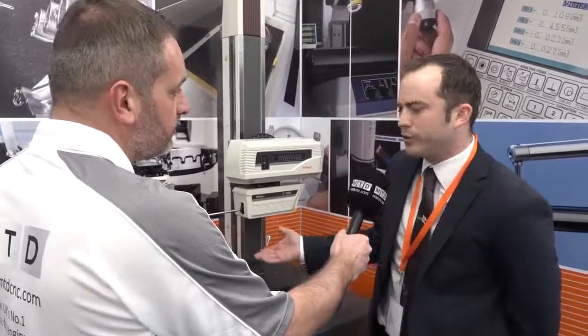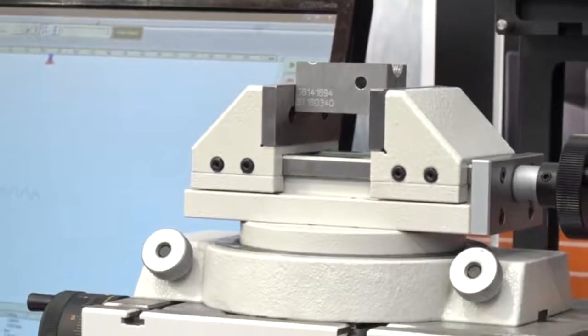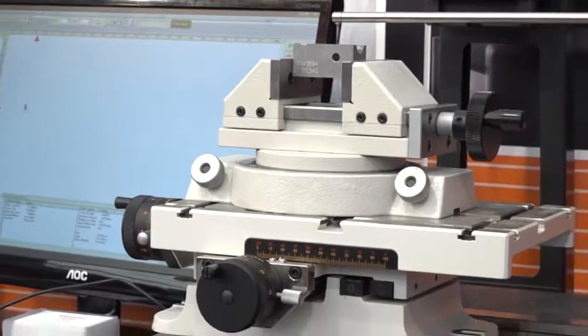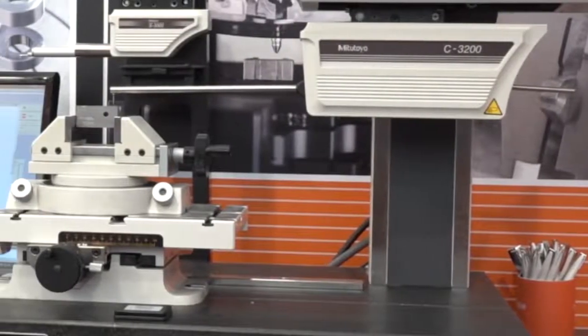This is the Mitutoyo C-3200 form tracer. This machine will measure both contour and surface finish by just changing over the measuring heads. We do have a machine where you can do it all with one measuring head, but the advantage of changing heads is we get a higher gauge range whilst measuring contour but still remain very accurate when measuring surface finish.